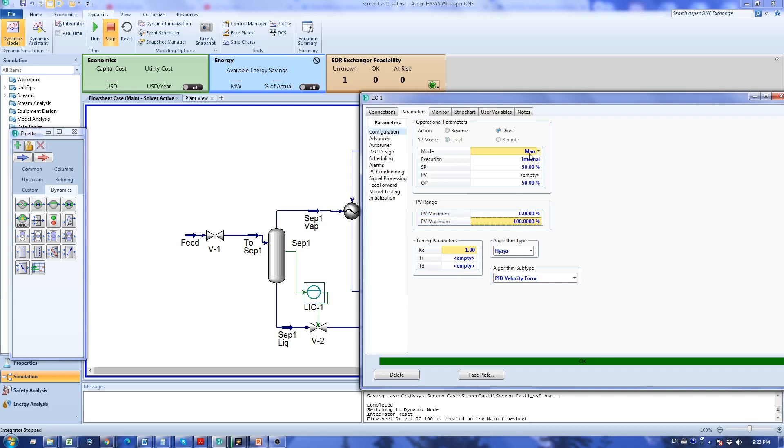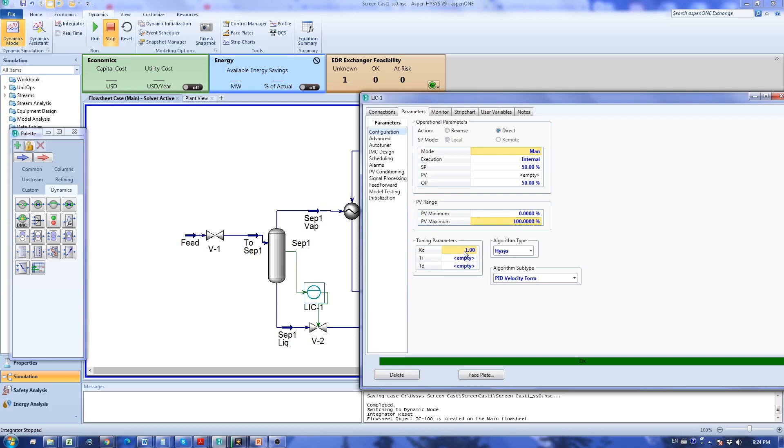For the tuning parameters, level control is pretty straightforward. We just use proportional controller which is the fastest type of control for the level. We are not concerned at keeping the level at a very constant value because there is already a surge volume inside the vessel. We're just going to keep this proportional controller with a typical kc of 2.